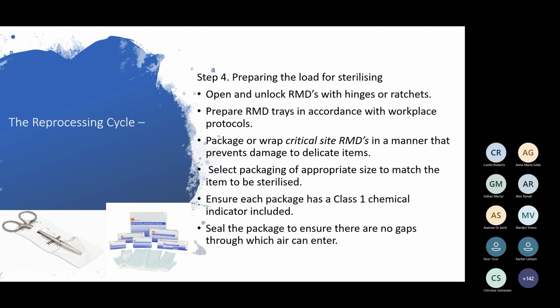So don't squeeze stuff into a little bag. Make sure that there's about 1 centimetre of spare space around the instruments in the bags. When you seal it, you want to do that because when the packs are inside the sterilizer, during the sterilizing process, when the steam's injected, it's going to puff that bag right up.